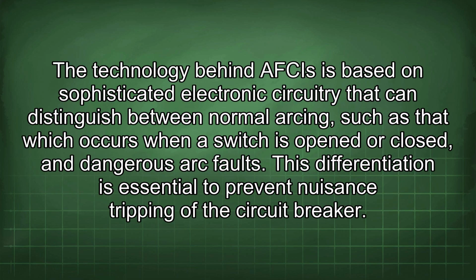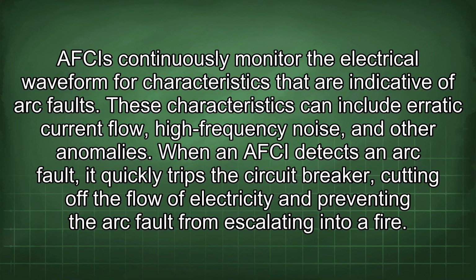The technology behind AFCIs is based on sophisticated electronic circuitry that can distinguish between normal arcing, such as that which occurs when a switch is opened or closed, and dangerous arc faults. This differentiation is essential to prevent nuisance tripping of the circuit breaker. AFCIs continuously monitor the electrical waveform for characteristics that are indicative of arc faults. These characteristics can include erratic current flow, high-frequency noise, and other anomalies. When an AFCI detects an arc fault, it quickly trips the circuit breaker, cutting off the flow of electricity and preventing the arc fault from escalating into a fire.